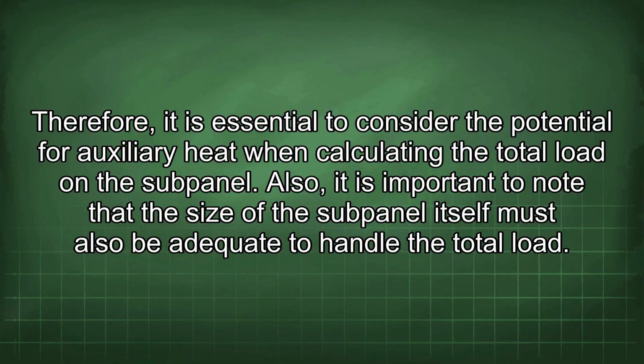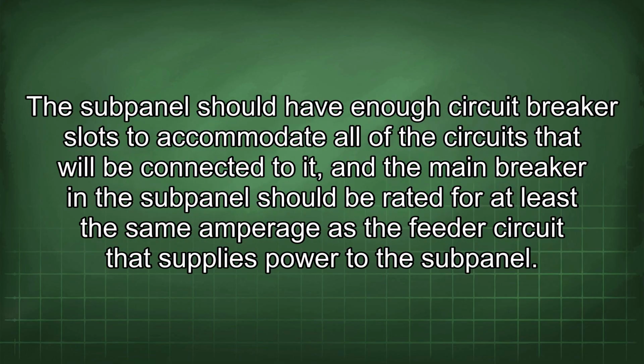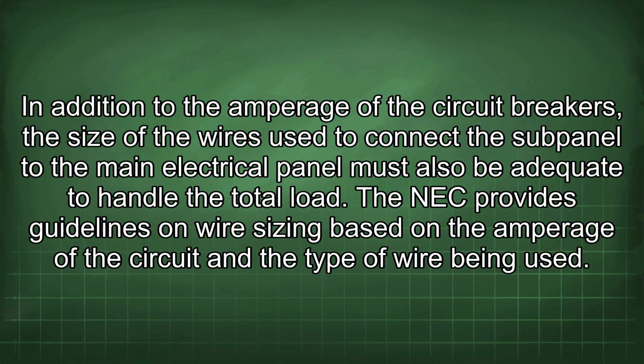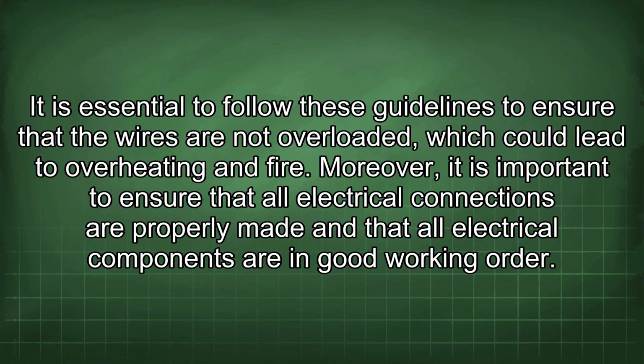Also, it is important to note that the size of the subpanel itself must also be adequate to handle the total load. The subpanel should have enough circuit breaker slots to accommodate all of the circuits that will be connected to it, and the main breaker in the subpanel should be rated for at least the same amperage as the feeder circuit that supplies power to the subpanel. In addition to the amperage of the circuit breakers, the size of the wires used to connect the subpanel to the main electrical panel must also be adequate to handle the total load. The NEC provides guidelines on wire sizing based on the amperage of the circuit and the type of wire being used. It is essential to follow these guidelines to ensure that the wires are not overloaded, which could lead to overheating and fire.